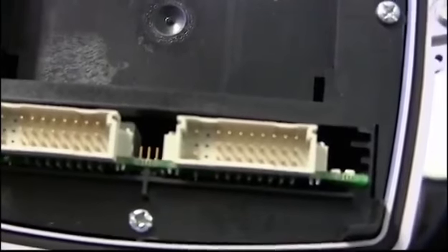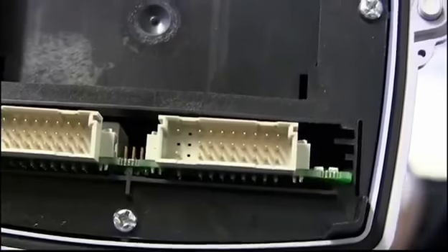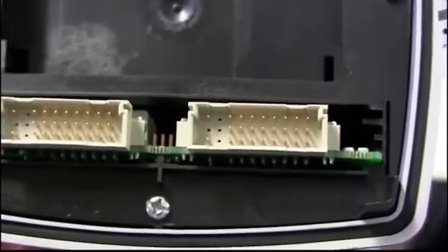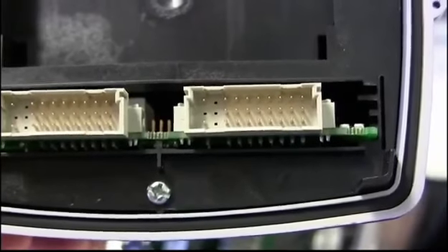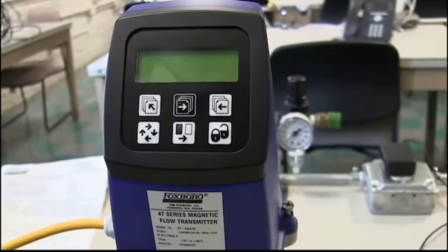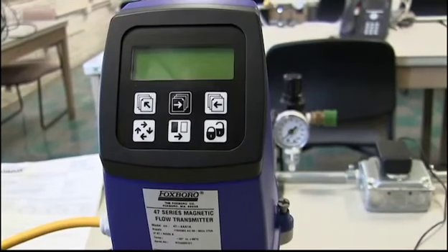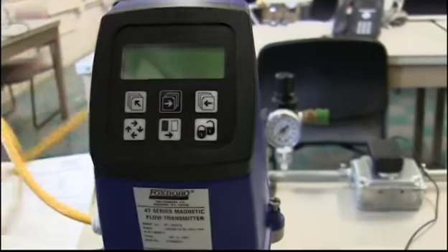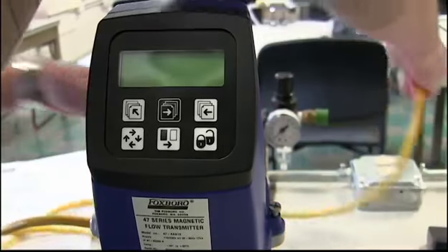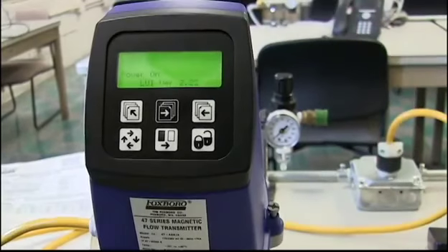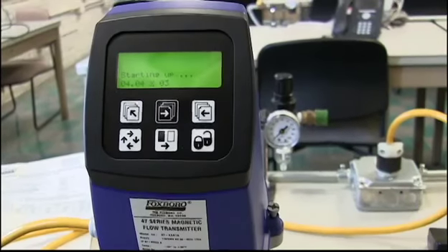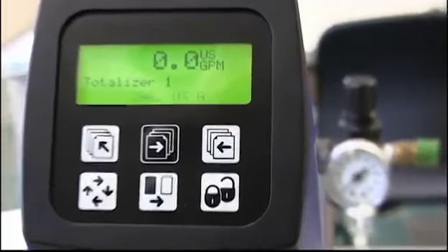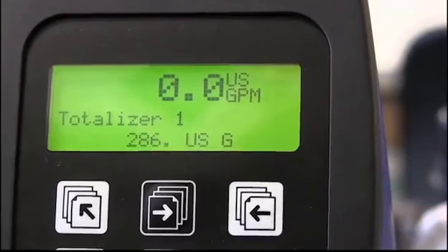You notice that there's some very fine pins here. As soon as we come into focus, I'll show you those. Okay, so they're very fine. So be careful when you put this transmitter down on top of that connector board. That way everything will come up in green when we plug it in. Okay, now that the transmitter has been placed on top of the flow tube, it's time to power it up. See what we get. Transmitter is powered up and it's going into the boot. Doesn't take long, and as you can see, we're already up and running.